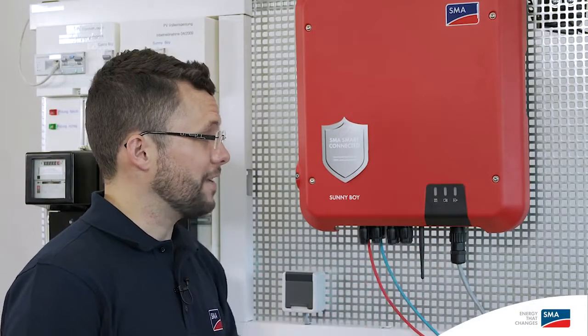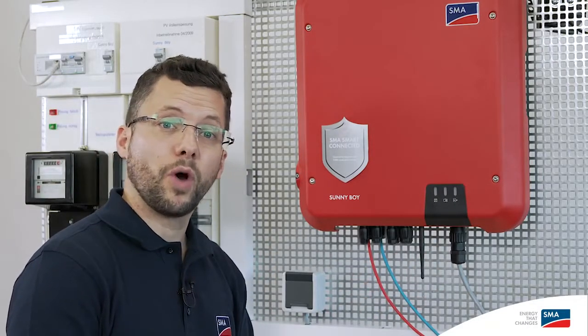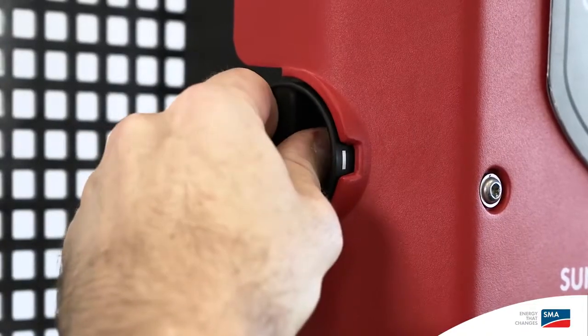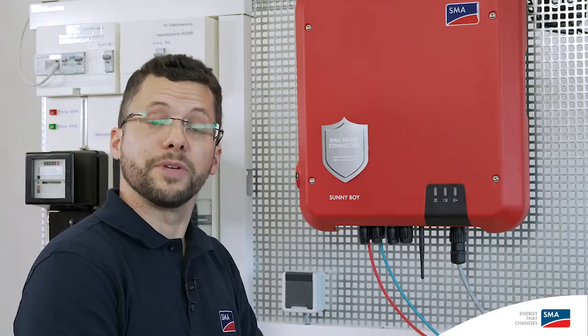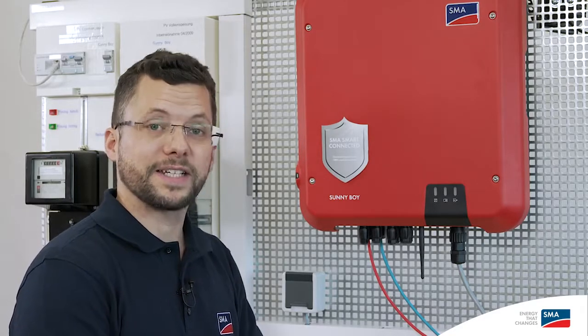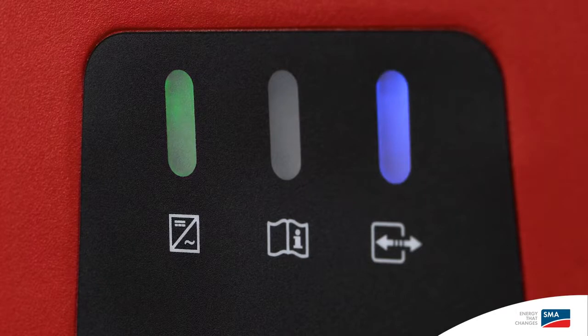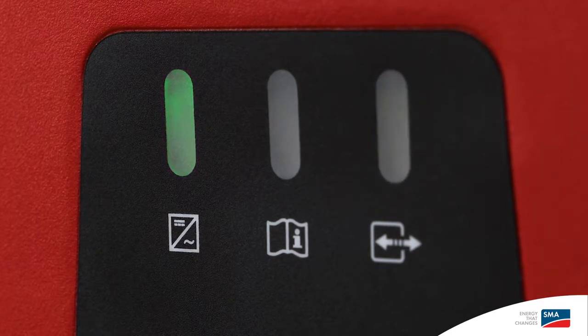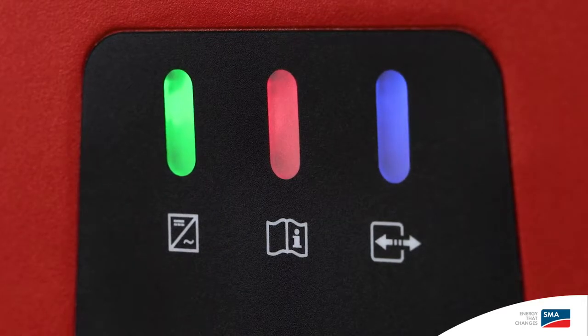So, now we can switch on the grid voltage on the AC side and confirm the DC disconnector is working. Mechanical and electrical commissioning of the inverter is now complete. There are 3 LEDs on the Sunny Boy cover. The green LED on the left is the operating light. The blue LED on the right indicates that the WPS function is active. When the red LED in the middle lights up, this indicates that there is a fault. In the event of a fault, the PV system operator and the installer will immediately receive a notification via email. Automatic inverter monitoring is a feature of SMA Smart Connected.